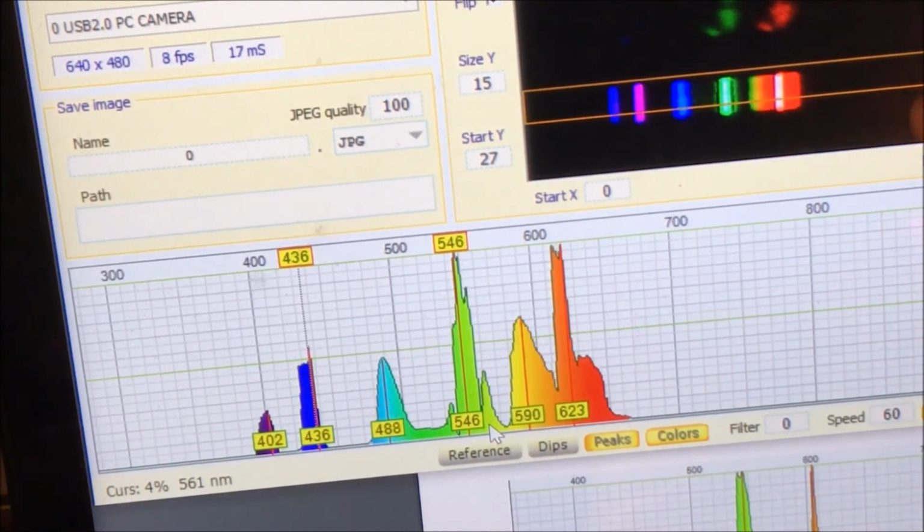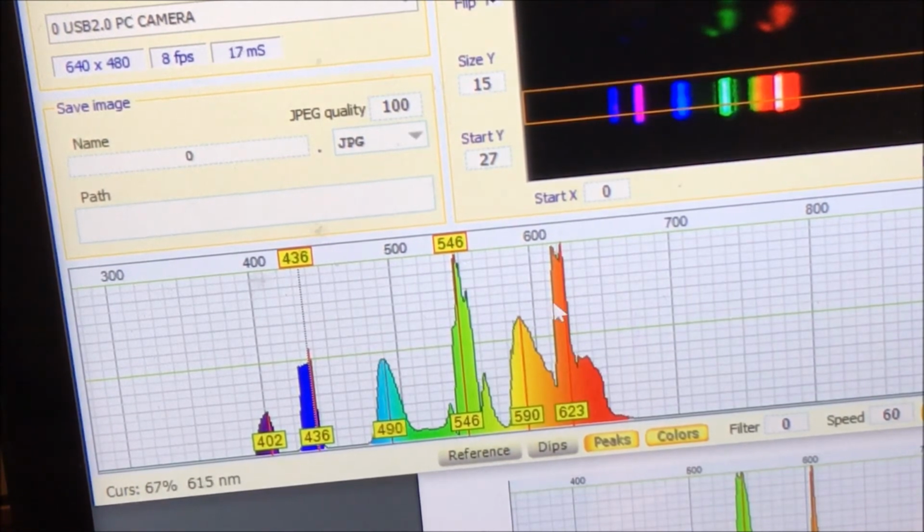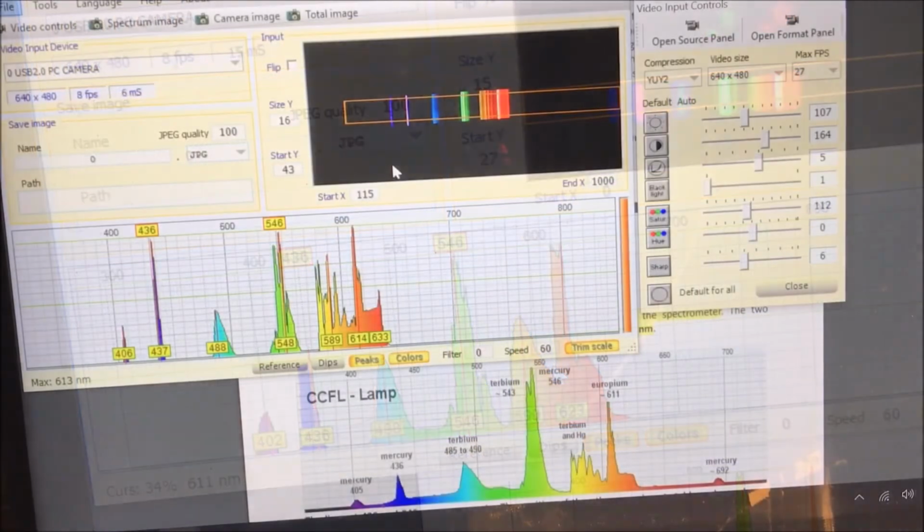And from this point on, we can go on and measure anything else, being confident that the values that we get and the spectrum that we get correspond to reality. Without this calibration, that is not really possible. You'll still get the characteristic peak positions, but you won't really know where in the visible spectrum they actually lie. This 546 could be 600 something if you don't calibrate it.